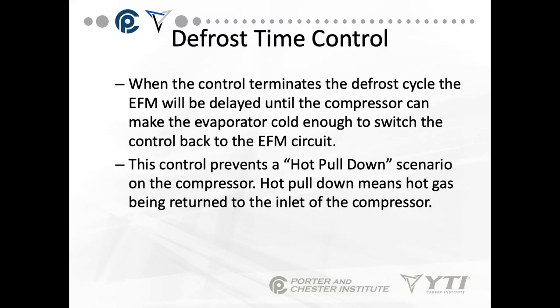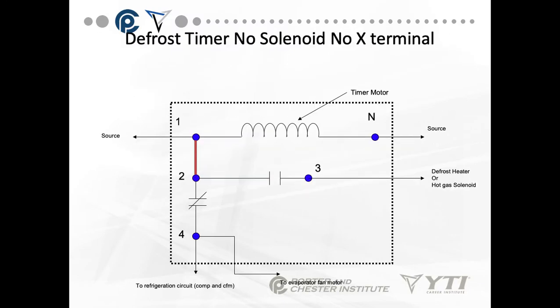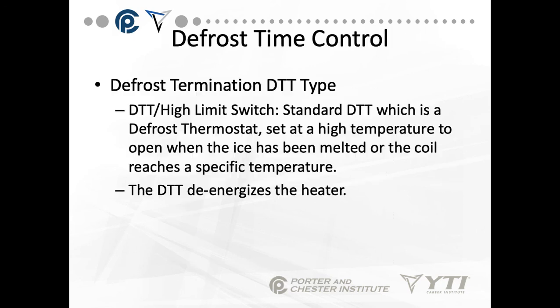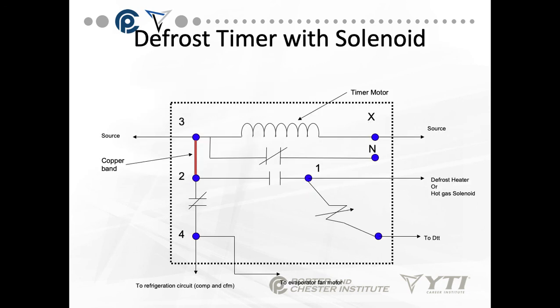Back to these diagrams — they're pretty important because you have to know what connects where. These don't have a defrost thermostat, but this one does. The clutch solenoid in the middle actually pushes the timer motor forward and will push the system out of defrost when the temperature of the coil gets hot enough. Whenever you have a chance, use the ones with the termination if at all possible.